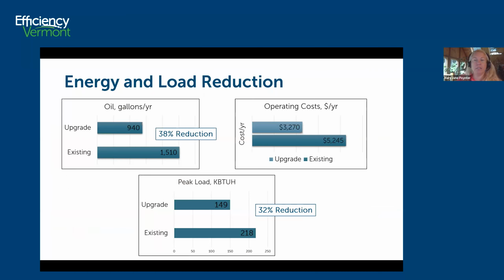So this is the impact on the load of the building. The existing was about 1,500 gallons of oil, and doing all those upgrades goes to 940 gallons of oil. That's pretty good just for thermal shell upgrades. So now instead of spending like $5,200 a year, they'd be spending $3,200 a year. And remember, the peak load that I showed you earlier was 218 and they have a 230 boiler. Now the peak load goes to 149. And you want to make sure that you have your blower door numbers to recalculate that.